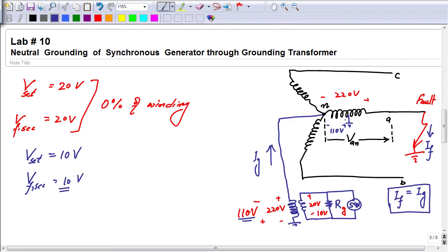But if the fault moves in this direction towards the neutral, then for each fault below this midpoint up to the neutral point, the voltage across the resistance would be less than 10 volt, and the relay would consider this condition as normal because the voltage is less than the pickup value. So here we can conclude that for the 20 volt setting of the relay, nothing of the winding was protected by this setting.